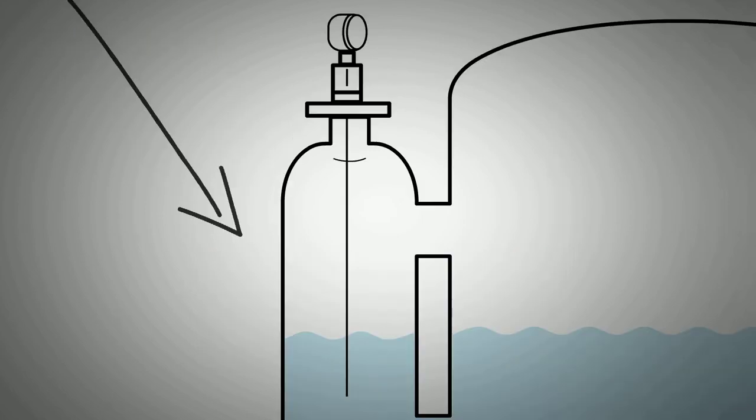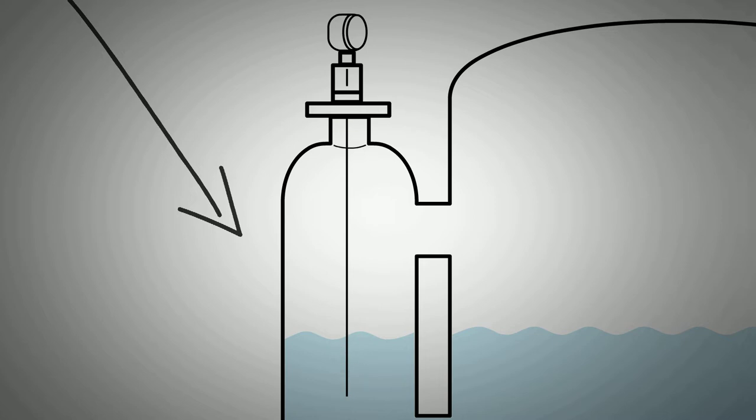The instrument works by emitting high frequency electromagnetic pulses. These pulses are conducted along a probe rod that runs into the media we wish to measure. When the pulses encounter the media, they are reflected towards the transmitter and picked up by a sensor.